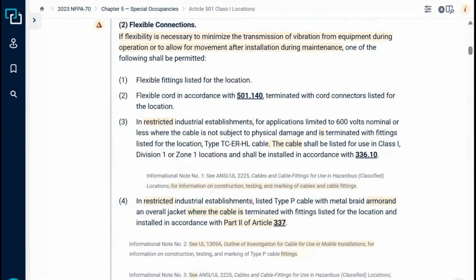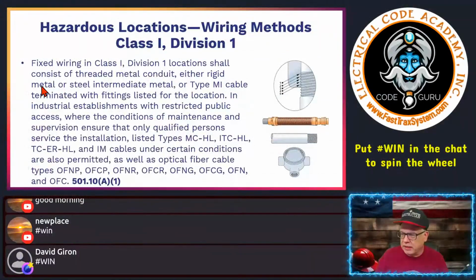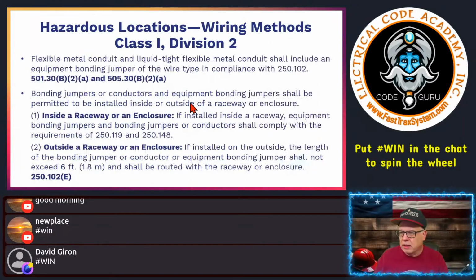Okay, let's get back to the lesson. So that's different things here. Now, Division 2 applications - wiring methods in Division 2 say flexible metal conduits and liquid tight flexible metal conduits shall include an equipment bonding jumper of the wire type in compliance with 250.102.